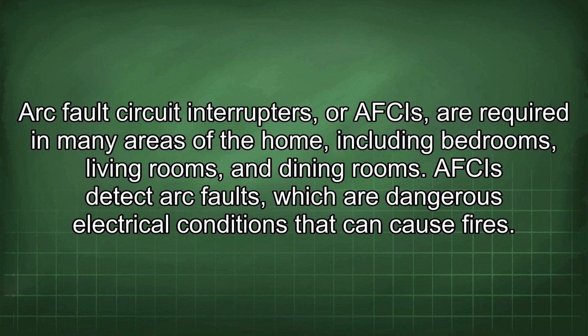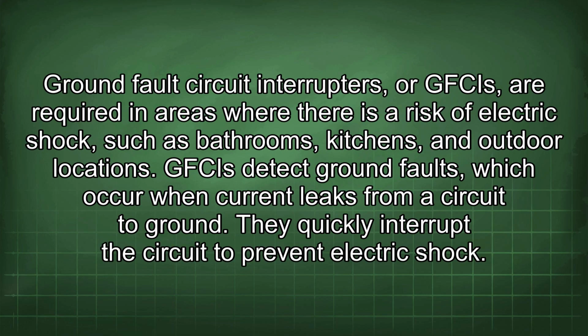Arc fault circuit interrupters, or AFCIs, are required in many areas of the home, including bedrooms, living rooms, and dining rooms. An AFCI detects arc faults, which are dangerous electrical conditions that can cause fires. Ground fault circuit interrupters, or GFCIs, are required in areas where there is a risk of electric shock, such as bathrooms, kitchens, and outdoor locations. GFCIs detect ground faults, which occur when current leaks from a circuit to ground. They quickly interrupt the circuit to prevent electric shock.